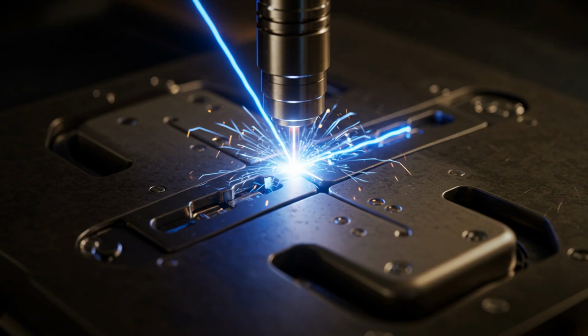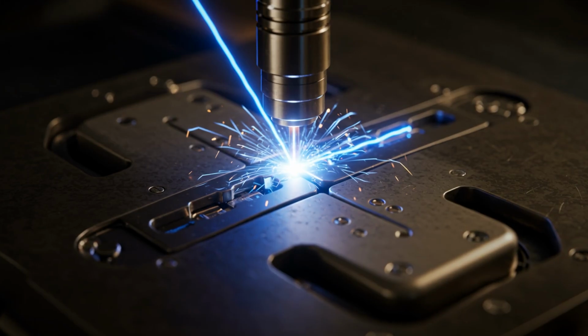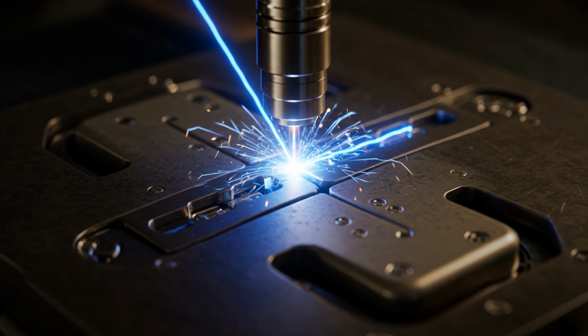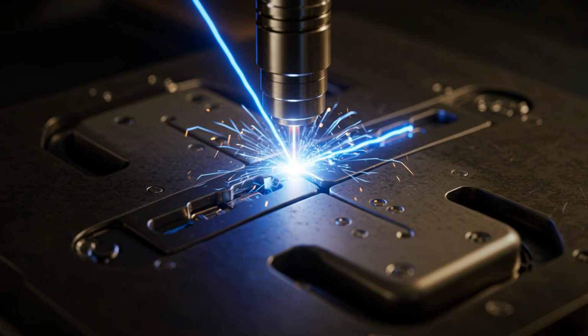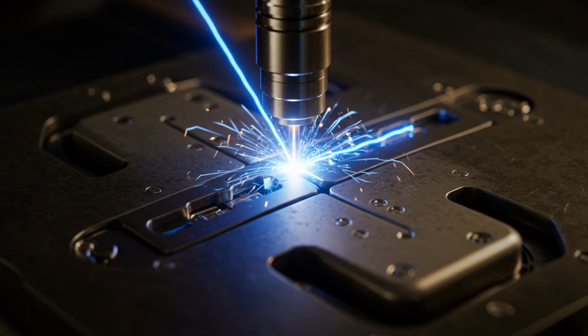How do you fuse two pieces of metal together without damaging the heat-sensitive battery just millimeters away? The answer is precision laser welding. The titanium halves are placed in an inert atmosphere, usually pure argon, to prevent oxidation. A high-energy fiber laser then traces the seam, focused to a spot size smaller than a human hair. The laser pulses so quickly that it melts the titanium locally, fusing the halves into a single continuous piece of metal, a process called hermetic sealing.